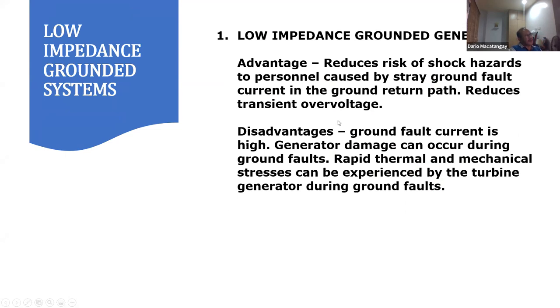Now, the disadvantage of this is that the ground fault current is very high because of the low neutral grounding resistance, and generator damage can occur during ground faults. Rapid thermal and mechanical stresses can be experienced by the turbine generator during ground faults.